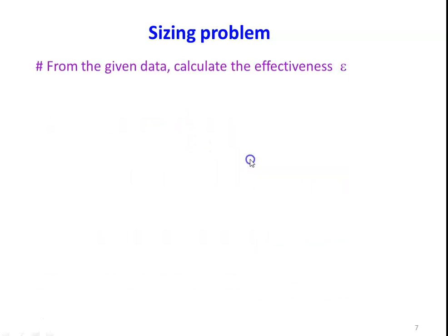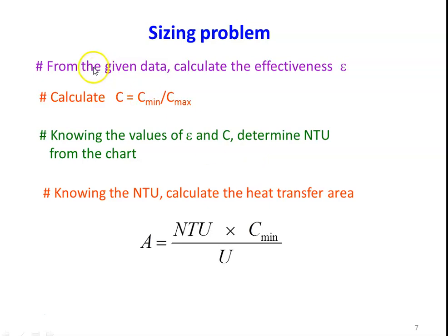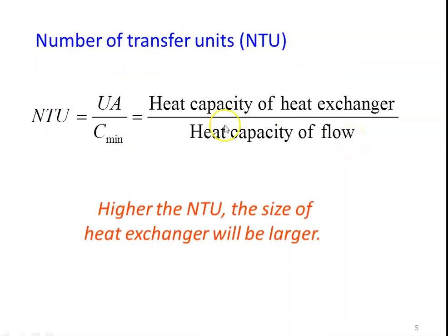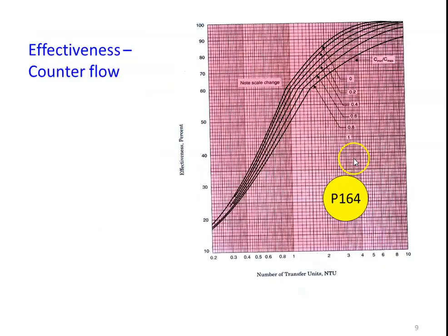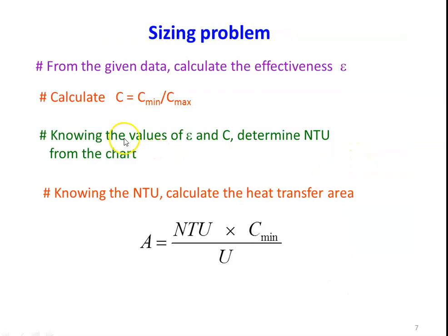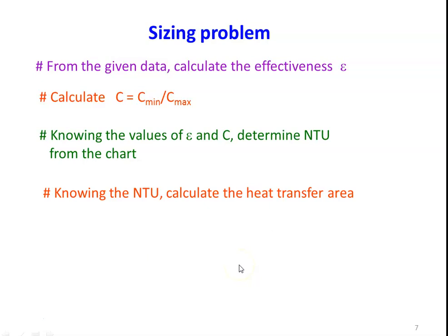For the Sizing Problem, from the data given, calculate the effectiveness of the heat exchanger using the relevant equations. Then calculate the C ratio: C minimum by C maximum. Based on the effectiveness and the C ratio, determine the NTU from the same chart. Knowing the NTU, calculate the area: Area equals NTU into C minimum divided by U. The procedure is similar — it may be a sizing or rating problem depending on the given data.